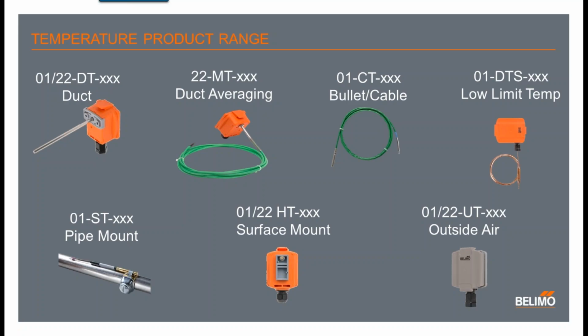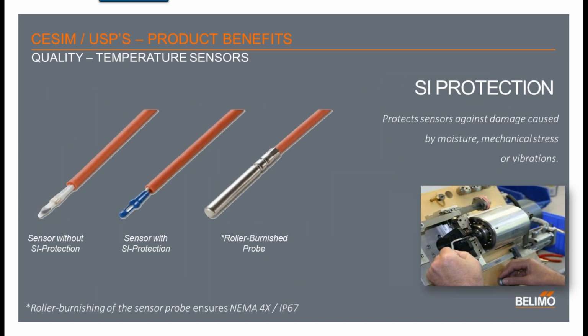So we have temperature sensors to cover all mounting types and all applications. We have duct sensors, we have duct averaging, cable sensors, low limit detection sensors for temperature, pipe and surface mount, and also outdoor air. All of our temperature sensors are protected from moisture by what we call SI protection. SI protection protects all of our sensors against damage caused by moisture, also mechanical stress and vibrations in the applications. All the probes have a stainless steel roller burnished probe which ensures NEMA 4X IP67 protection.